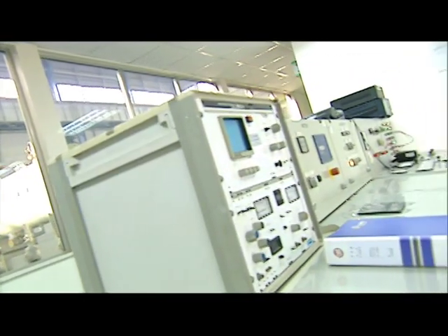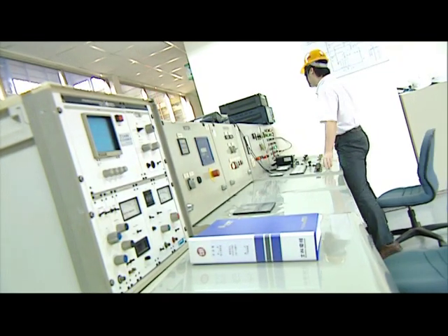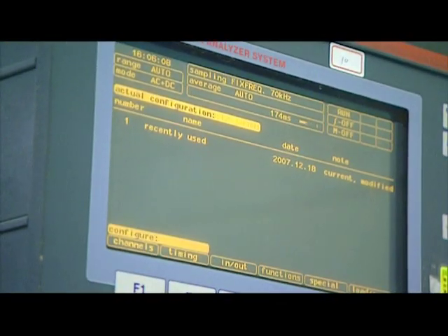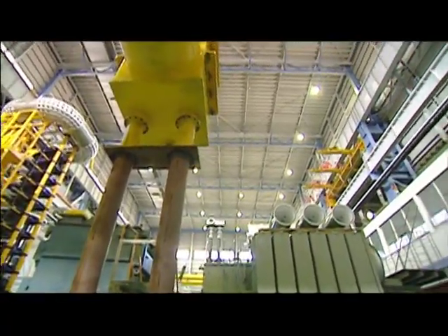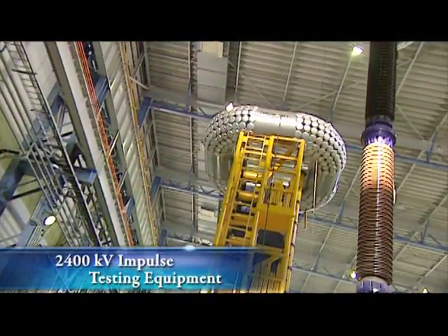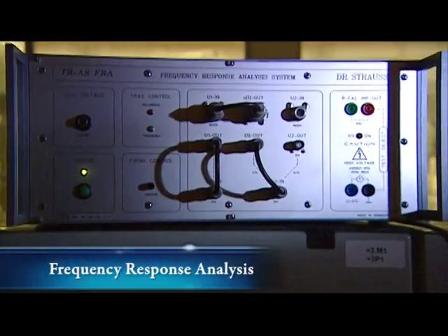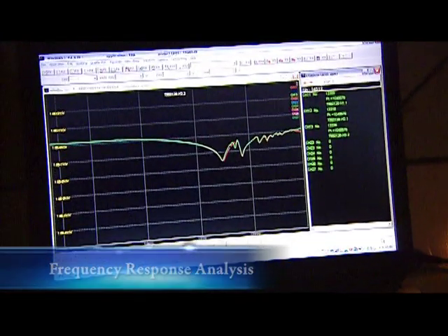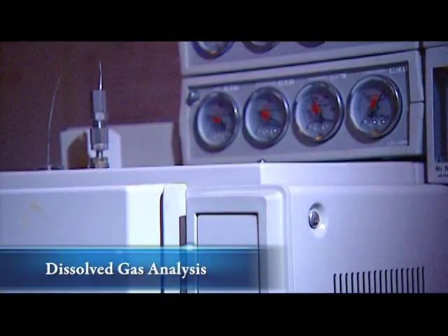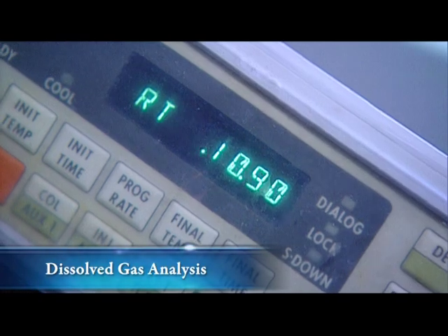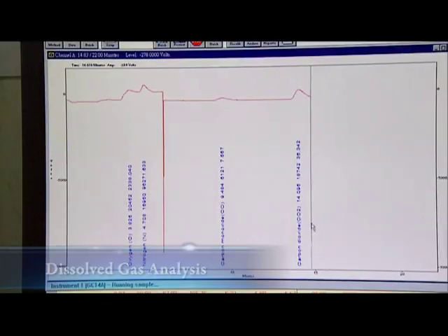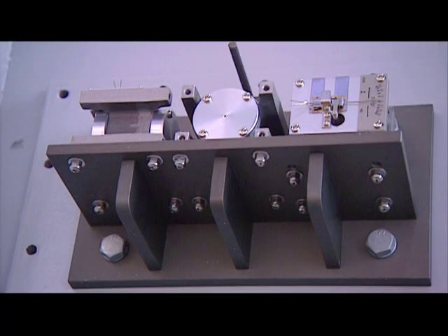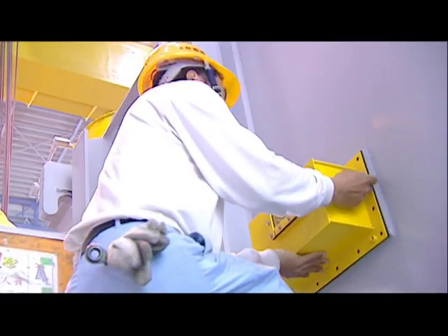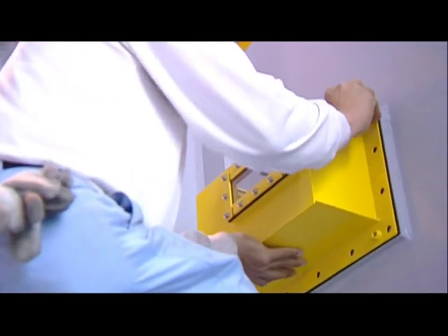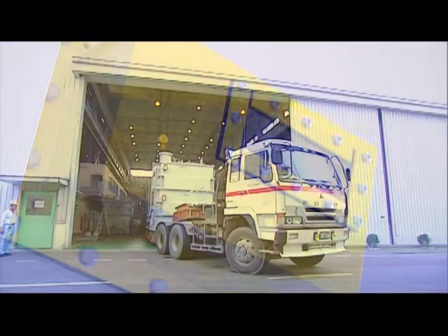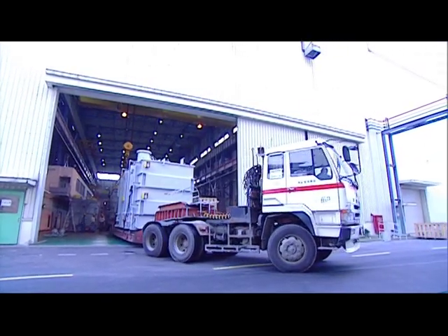SHIHLIN Electric heavy electric plants conduct in-house quality inspections in specifically designed high-precision test centers. Installed test equipment include a 2400 kilovolt insulation endurance testing machine and a TOGAS precision oil immersed gas analyzer for testing hydrogen, carbon dioxide, and ethane gases in insulating oil in order to guarantee optimal insulation effectiveness. State-of-the-art test centers guard the front lines of SHIHLIN Electric's exceptionally successful quality assurance program. This ensures each product meets strict quality requirements before being released for installation and use.